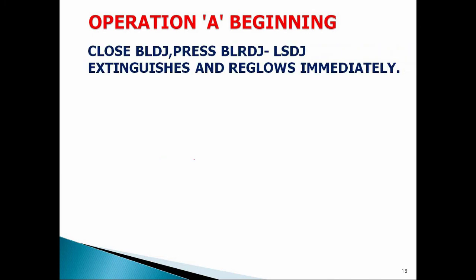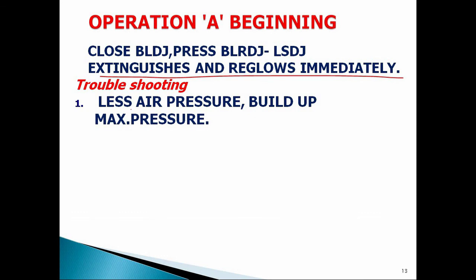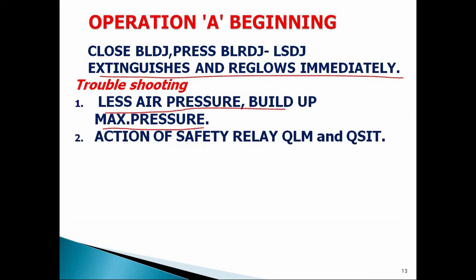Troubleshooting for next abnormal sign picking up, that is operation A beginning. Operation A beginning abnormal sign is close BLDJ and press BLRDJ, LSDJ extinguishes and reglows immediately. So the troubleshooting procedure is, ensure the RS pressure is more than 6.5. If it is less, start MCPA, build up RS pressure, and check relay targets QLM and QSIT. If any one of those is energized, troubleshoot for them, and if they are not energized, try to reset or rotate the knobs once and try to close DJ.